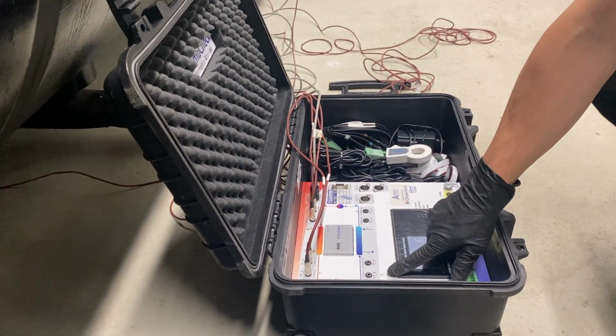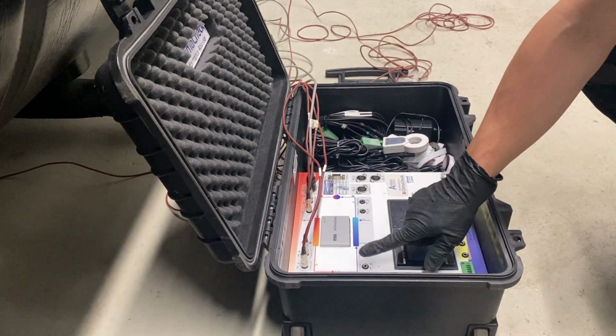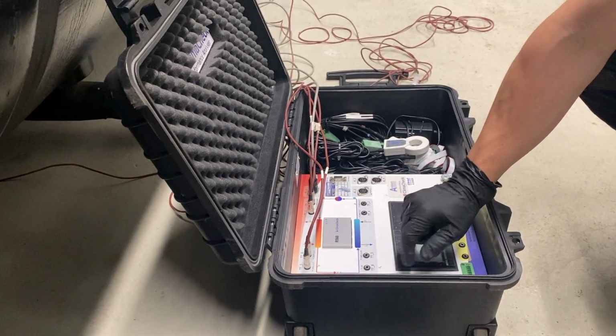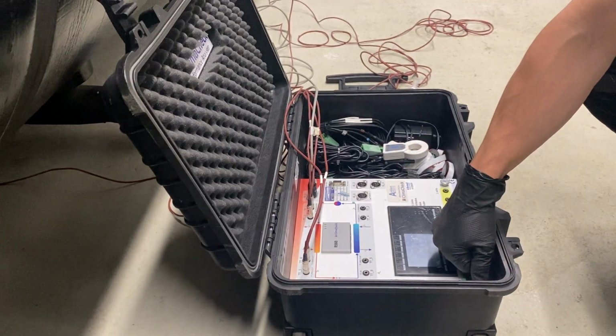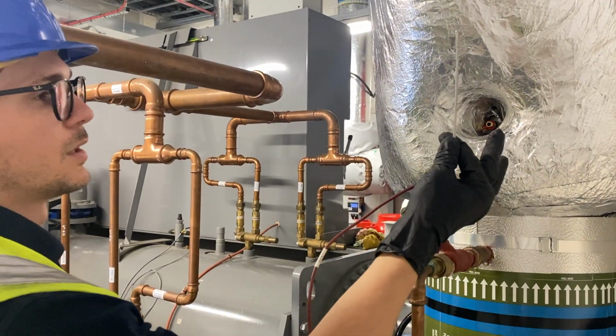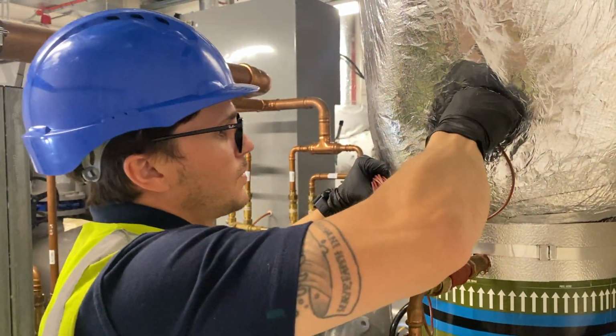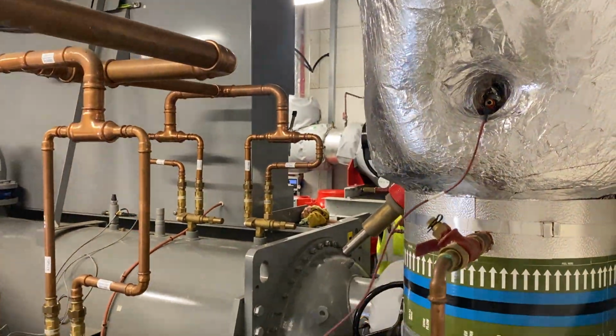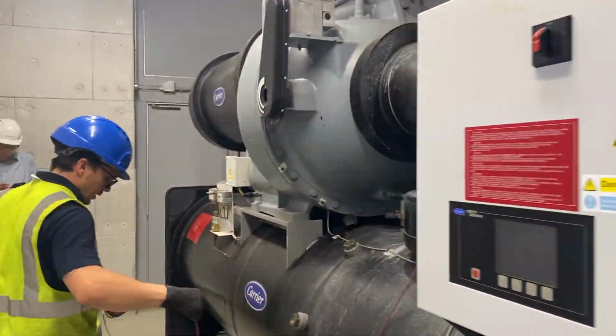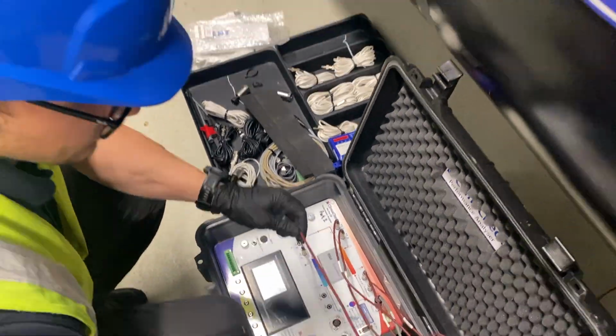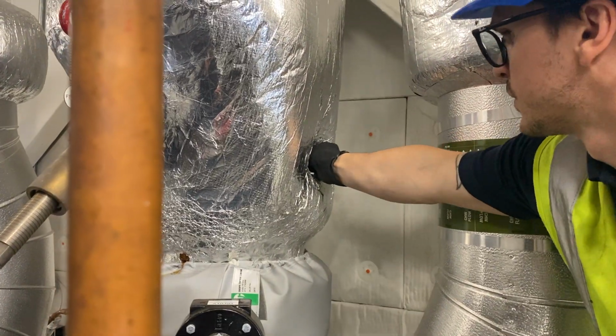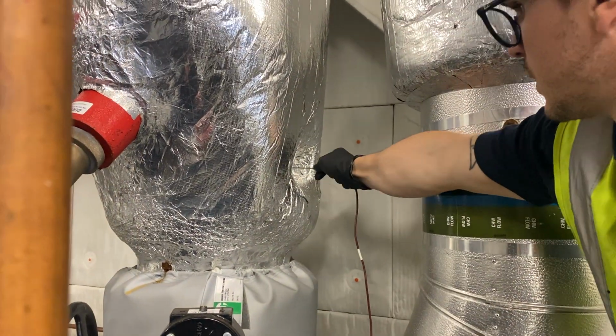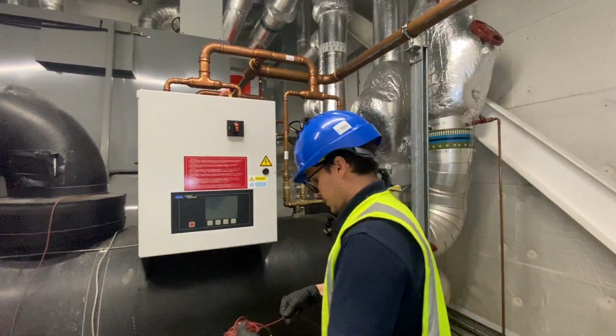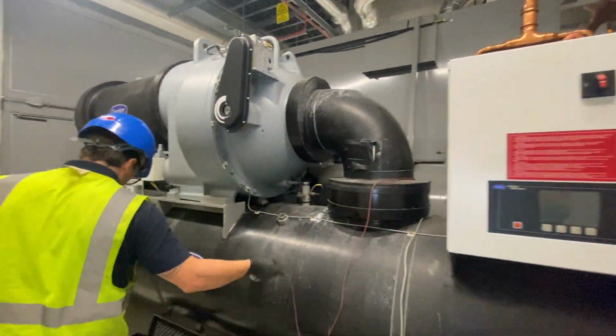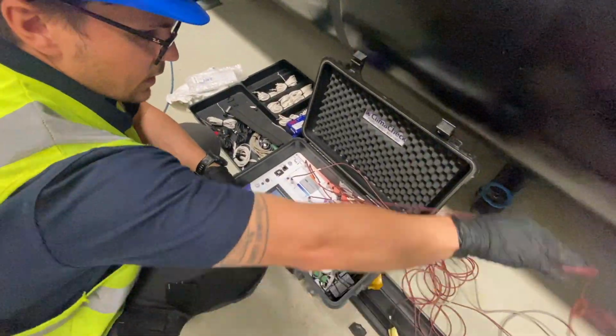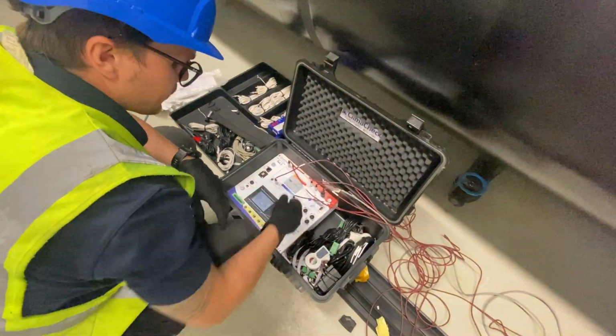Next we are pointing out the next one to be dealt with, the chilled water leaving temperature socket. Installing the probe in the available temperature well. Doing the same with the chilled water inlet temperature, installing the probe. Next we are plugging into the TT4 socket, which is the chilled water inlet temperature.